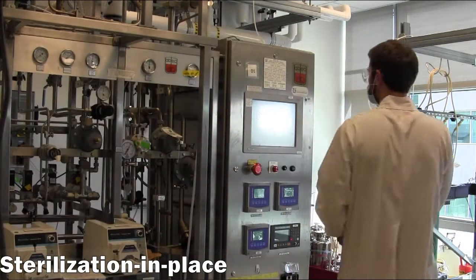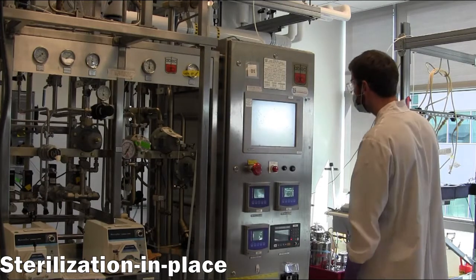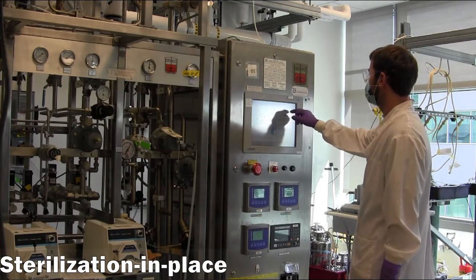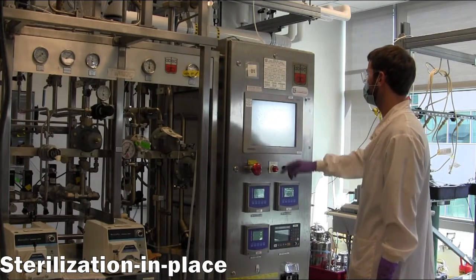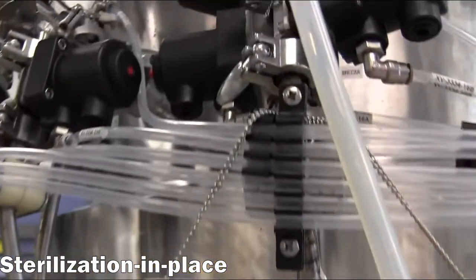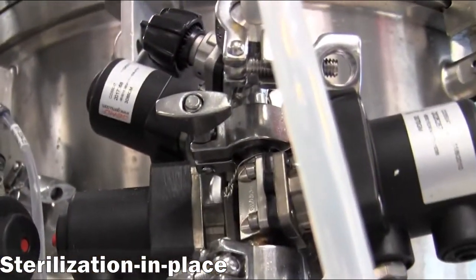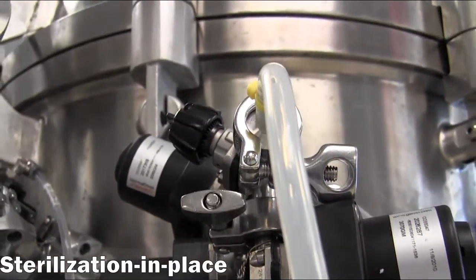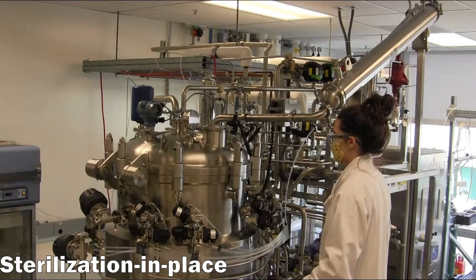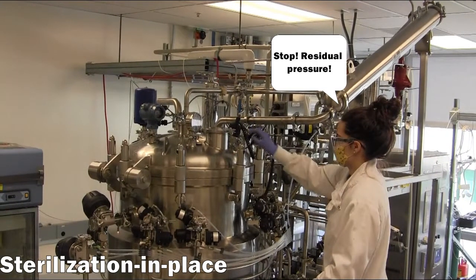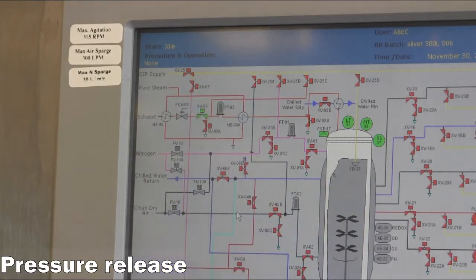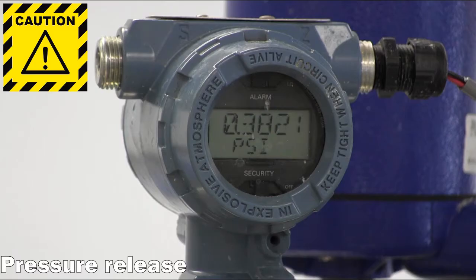Another important procedure to execute as part of the functionality checks is the sterilization-in-place procedure. The cycle is performed before the media is made up to test heating and cooling functionality of the reactor and provide an estimate of how much condensate is added during an SIP cycle. This information is used later when batching the media. As always, check the residual pressure before opening the reactor through the head plate, using XVO3 to release pressure if necessary.